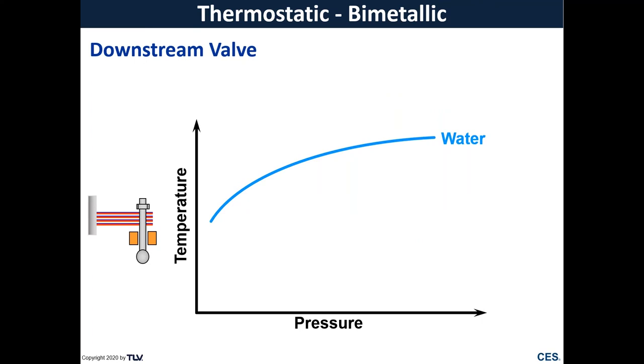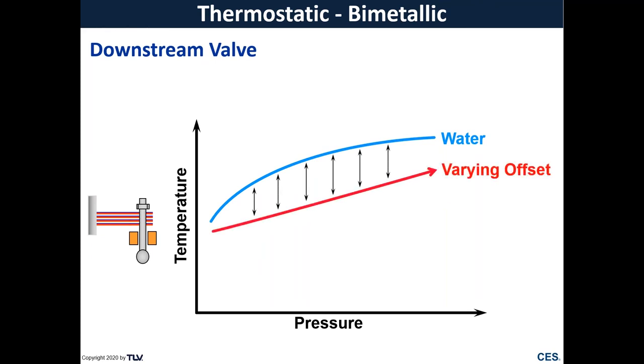There's a few more things to consider with a downstream valve head, as the downstream valve head is going to have to work against the upstream pressure. So it's actually going to give us a varying closing temperature. As you increase that inlet pressure, that's going to cause the bimetals to have to pull back even harder against that valve head in order for the trap to close. Again, the idea here is still to set that closing point lower than our steam temperature.